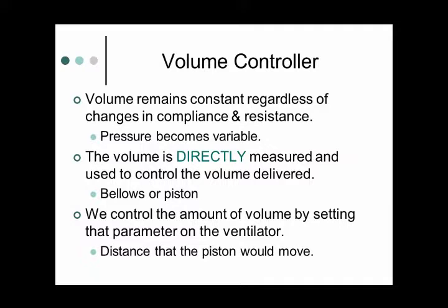And really the only instances of these are piston-based ventilators. Okay? So with a piston, it pulls the piston back, fills that chamber with gas, and it delivers that entirely. So the volume never changes on a breath-by-breath basis. Okay? It's a volume-oriented breath, but I'm going to take a little twist on this in a second.